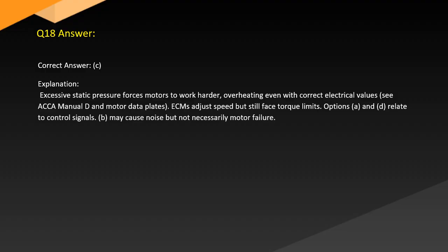Answer. Correct answer, C. Explanation. Excessive static pressure forces motors to work harder, overheating even with correct electrical values. see ACCA Manual D and motor data plates. ECMs adjust speed but still face torque limits. Options A and D relate to control signals. B. May cause noise but not necessarily motor failure.